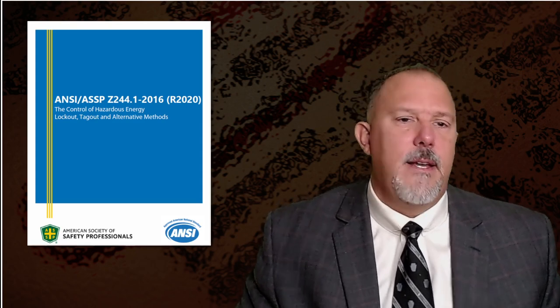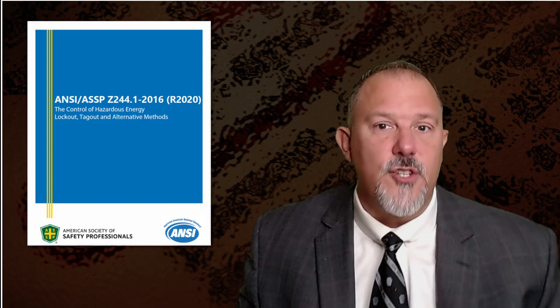We're in between first draft and second draft right now. But once this cycle finishes out, this is going to be a shell document. This needs to be a part of your library regardless. 70B is an important aspect. Maintenance, condition of maintenance, is critical for safe work practices. It's critical for recognizing hazards. 70B, keep that on your radar. And I'm going to give you another reference. This is from the American Society of Safety Professionals, ANSI, ASSP. This is the Control of Hazardous Energy, Lockout, Tagout, and Alternative Methods. Great reference, great resource. I think it's something also worthy of your library.